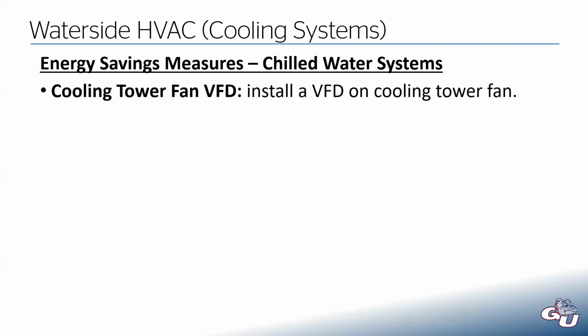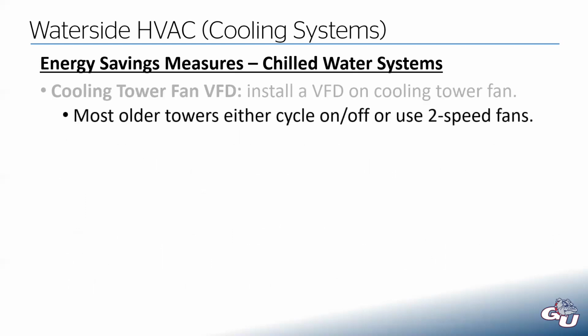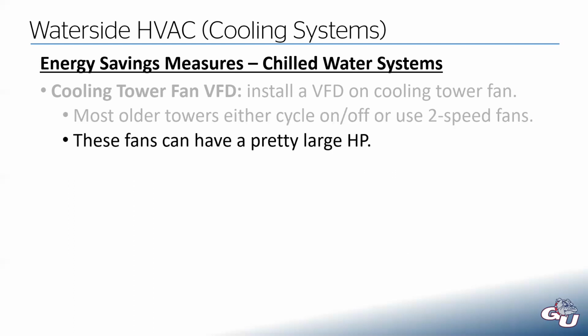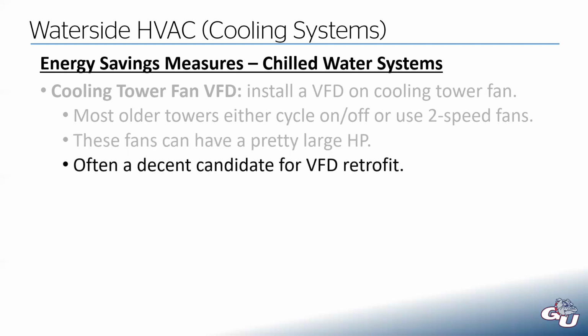You could convert your cooling tower fan to a VFD controlled, add a VFD to provide speed control. So you install a VFD on the cooling tower fan. Most older towers either cycle on and off, or they use 2-speed fans. And so a cooling tower fan VFD could save a lot of energy. These fans could have, or I should say often have, a pretty large horsepower requirement. And the larger the horsepower of the fan, the better candidate it's going to be for a VFD retrofit.